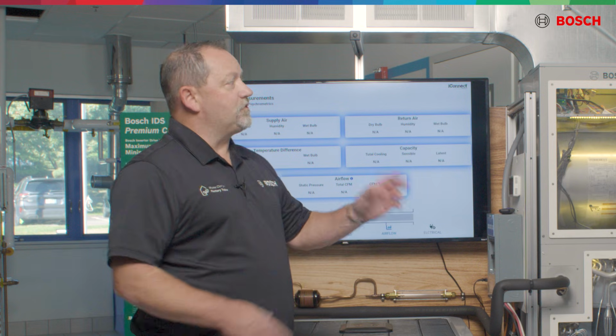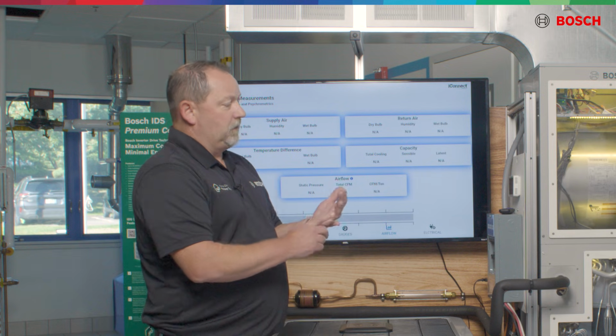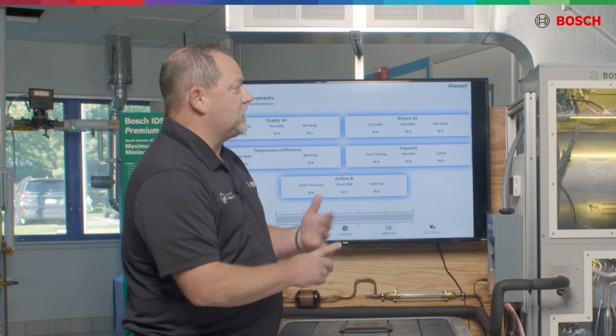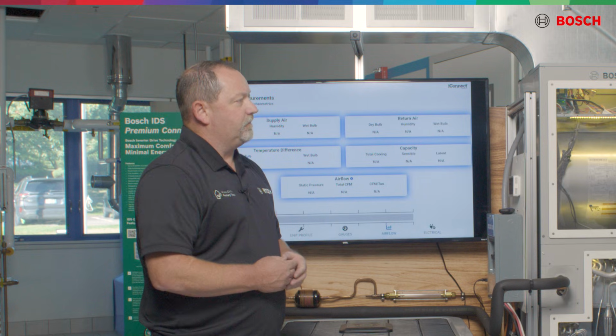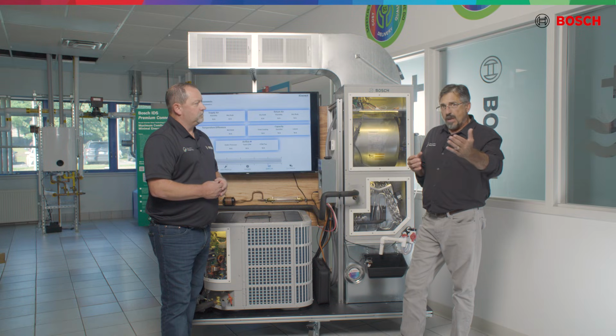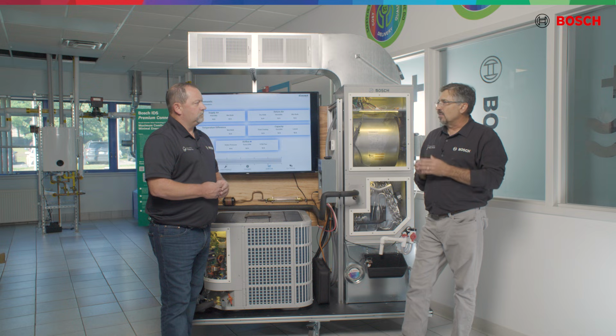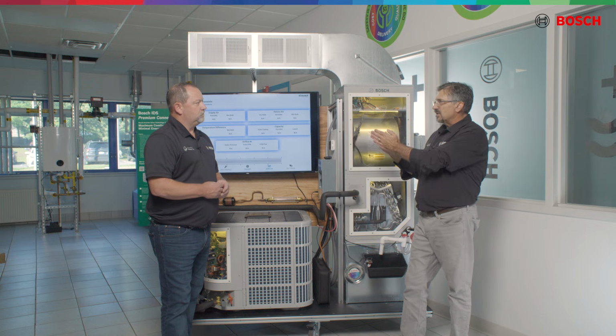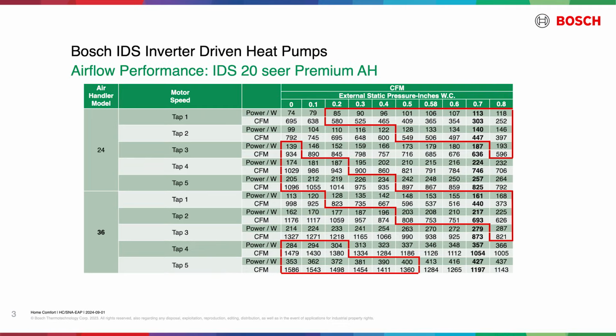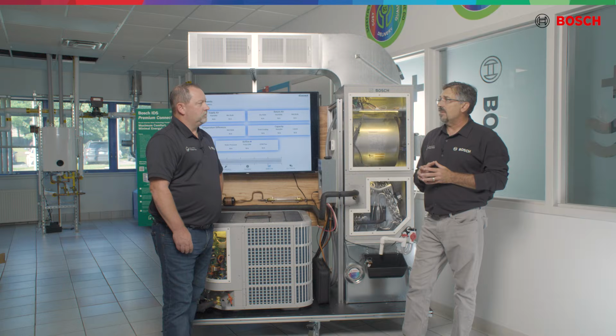So you mentioned static pressure. I needed to collect static pressure. Before we do this calculation, what are a couple other things that we need to collect? Well, when we get our static pressure, we're going to go to a Bosch blower performance data chart, and we're going to prove at what static pressure, how many tons the blower motor is, how many CFMs we are delivering. And right now with inverter-driven technology, we want 350 CFM per ton. This is a 3-ton unit. I'm looking for 1,050 CFM.